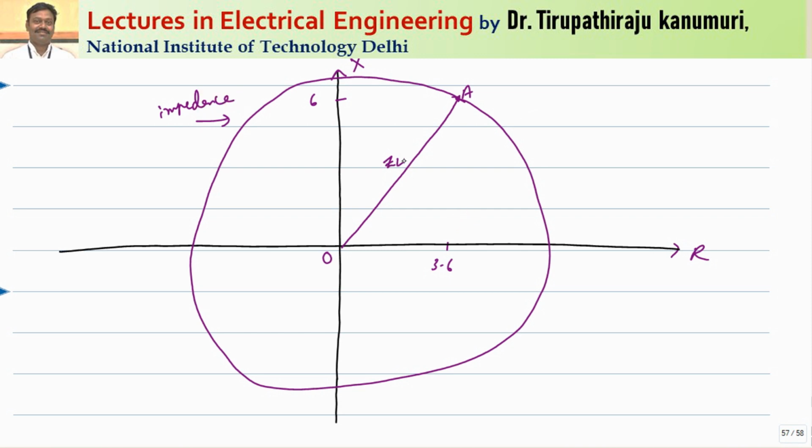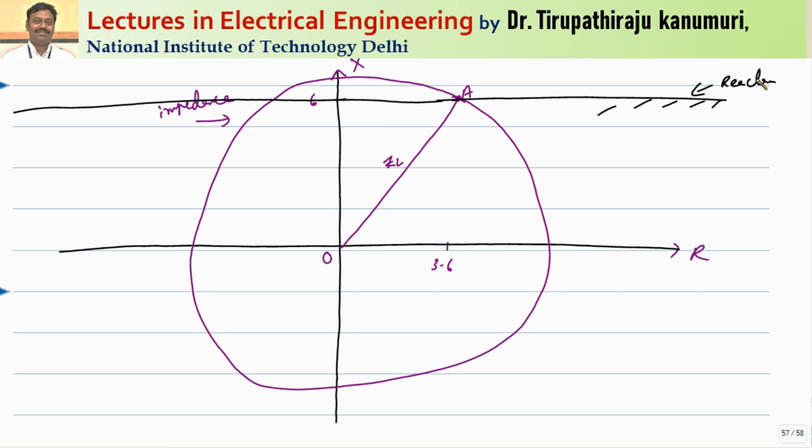Now coming to the case of the reactance relay. Because I have to protect up to this instant, draw a straight line up to this point. That gives your reactance relay. So the reactance relay characteristic, I can draw it like this. In this region it will operate. So if the value of X is less than 6, it will operate. The reactance relay will come at jX6 or corresponding to 6. This is j6. Getting this one, reactance relay is done.